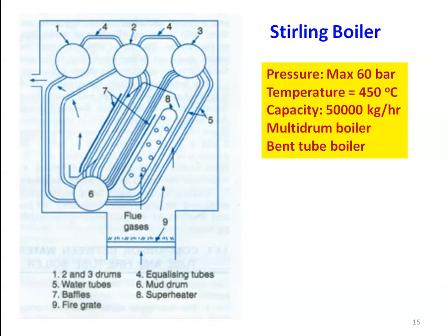We have baffle plates — number seven. Number eight is the superheater; we have a bundle of superheater tubes. Number nine is the fire grate, where the burning of the fuel takes place. Number four is the equalizing tubes — equalizing tubes means that in all three drums we have to maintain the same level of water and steam, so we connect the three drums to equalize the levels. One advantage of the bent tube is that because of heating, the tube material will expand, and because of the bend, the expansion will be accommodated easily, so overall structural problems will not occur in the Stirling boiler.